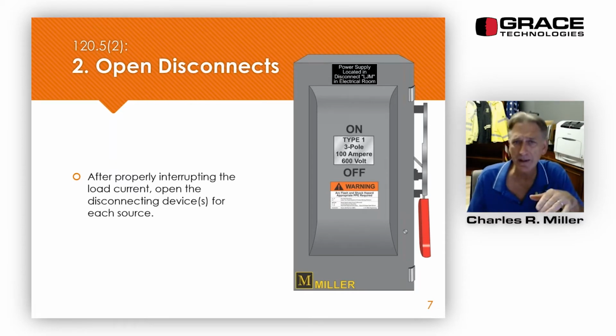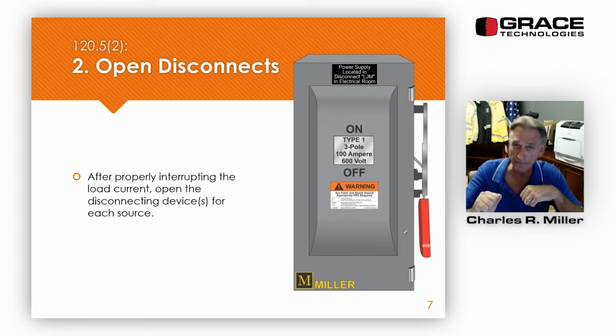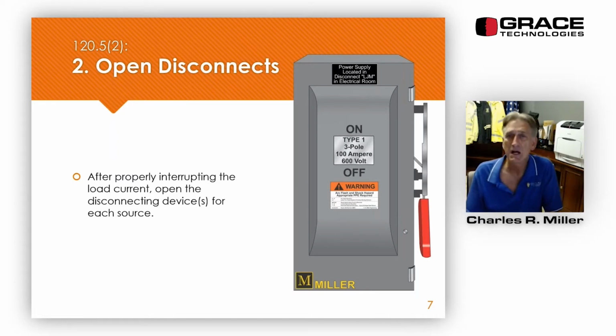But what is it talking about with load current? Old disconnects, you could pull up the handle and turn it on as slow as possible or off as slow as possible. But typically disconnects now are spring loaded, or a lot of them. The smaller ones are still not, but a lot of the bigger ones, 100 amp or more, are spring loaded, where it kicks in, pulls the blades in very fast and pulls the blades out very fast. And so this is what it's talking about, load current rated. Not all disconnects are load current rated.